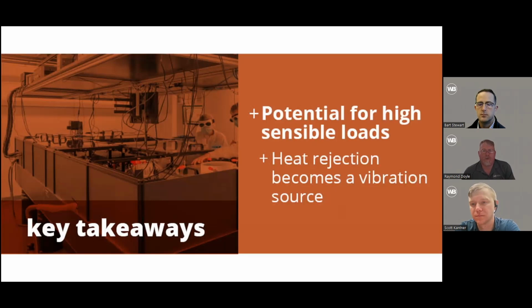Then we talk about high power needs. High power needs turn into high sensible heat loads, which is just the need to reject the heat generated inside the lab. When that happens, you end up with a large heat rejection system, which could be chilled water, refrigerant, or air. Any of those heat rejection systems generate vibration in the space and create problems you need to mitigate later. So understanding that those high sensible heat gains are something you'll need to deal with lets you plan ahead for where those things will be located to mitigate that vibration.